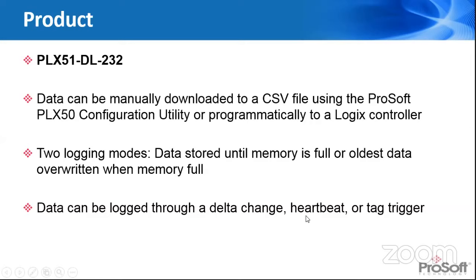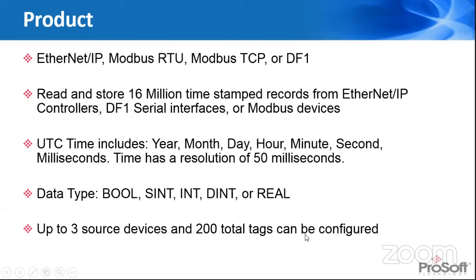So you've got some different trigger options in there. The module itself supports Ethernet IP, Modbus RTU, Modbus TCP/IP, or DF1. So it can be used with our Rockwell PLCs, with Modbus TCP/IP or Modbus devices, and also with DF1 if you had a SLC processor out there that you wanted to log data from.